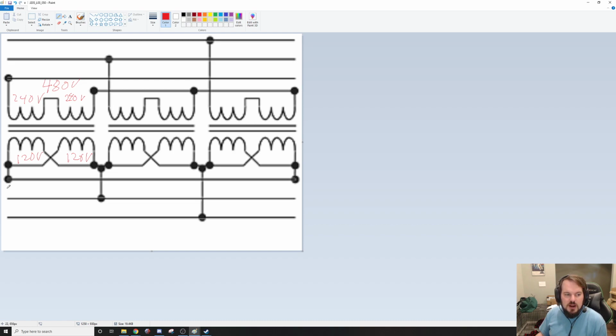Then down here, if these were 120 volt coils, them being wired like they are, any current would have a way to choose its direction, which makes it parallel. So these two parallel coils would make this 120 volts, because in parallel, voltage stays the same, and in series, voltage adds up. So you have high voltage, which makes them in series, and low voltage, which makes them in parallel.